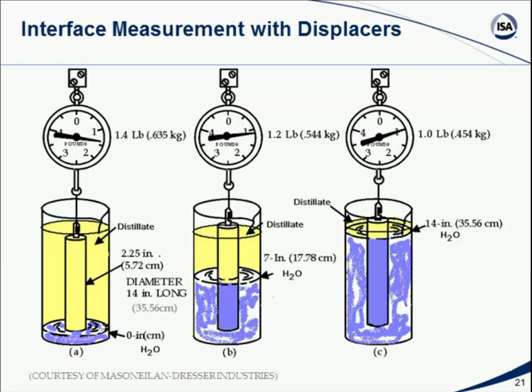All right, so we started this first section by talking about level. What do we mean by it? Are we talking about a measurement from top or bottom, or how much is in the tank? Are we talking about knowing whether a level is above or below a certain point, or exactly what the level is? We've talked about a variety of different measurement types of devices: dipsticks, steel tape, float systems, and then the use of a principle of buoyancy with displacer technologies. So we've covered a variety of different topics, and at this point we're at the end of section number 1.